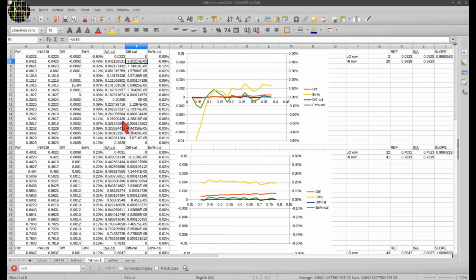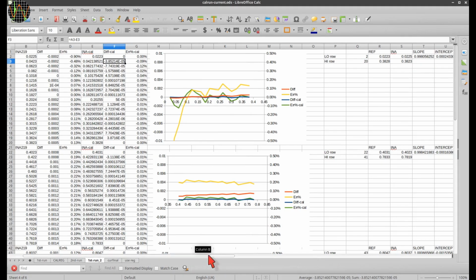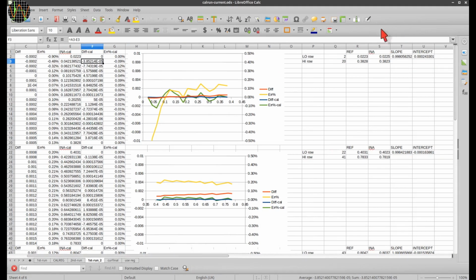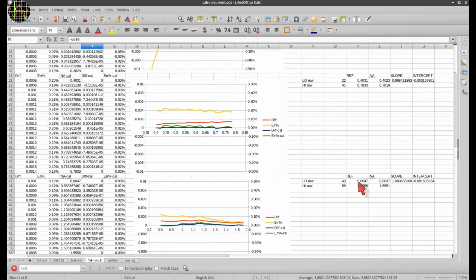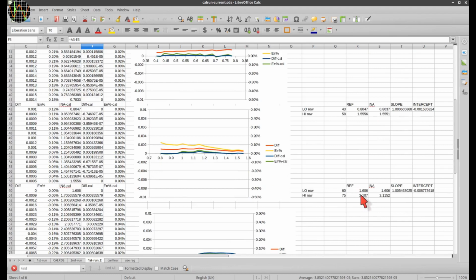A simple scale factor isn't going to correct this data, but if we use the same slope and intercept method I originally intended for just the bus voltage calibration, things improve drastically. Here you have the same data, but this time I picked 2 rows for each range to calculate the slope and intercept, as you can see here, for each of the 4 ranges.